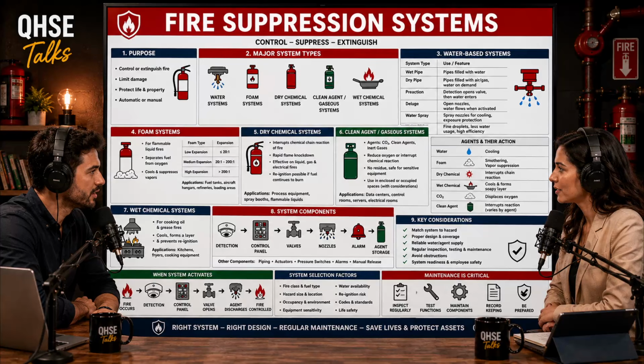That's a deep dive mechanical inspection, almost always performed by a certified outside contractor. They take it off the wall, examine all the mechanical parts, the valve assembly, and potentially empty and refill the agent. And the final, most intensive level is hydrostatic testing at 5 or 12 years. What exactly is a hydrostatic test and why is it necessary?